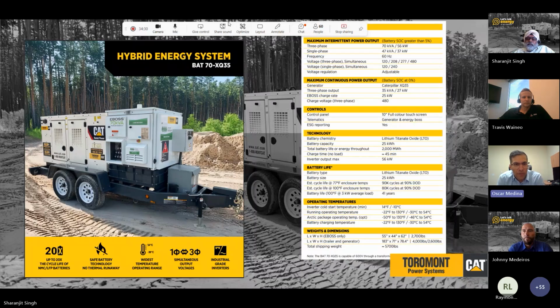Yeah, so currently we have two of these products in our fleet. The first one is the battery, the 70, that is paired with a XQ35 kVA CAT generator. This unit can do 208, 480, and through a transformer, if you see it in the picture, can do 600 volts at the same time. This unit is 25 kilowatt hour. And the charge time is 45 minutes. The life of the battery is around 80 to 90,000 cycles. And the good thing about both units that we're going to present today is that they can manage the cold temperature. They come with a cold weather package, and the range could be around minus 46 degrees. That one's the first one.